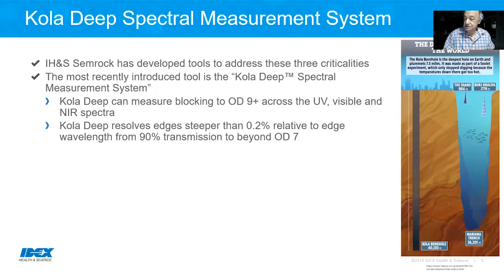So to show the kind of performance that's achieved here, one can look at this MaxLine filter at 248.6 nanometers, and look at the theory, which shows the spectral edge on both sides of the laser line, and the Kola Deep system measurements, which track it extremely well down to about OD7 or so. And then one can also see that the standard spectrometer will show results that deviate starting around OD3.